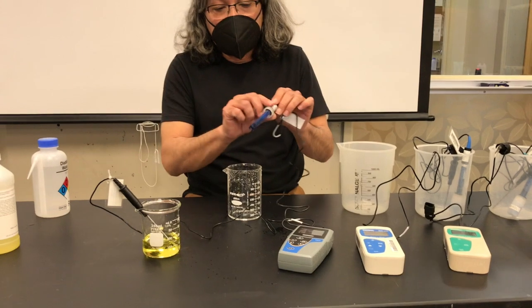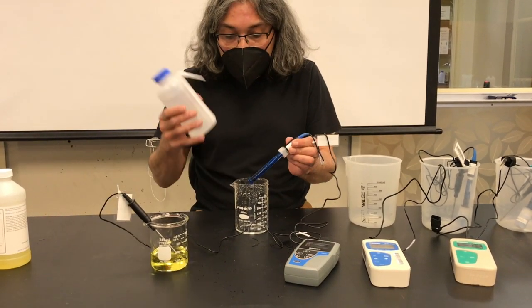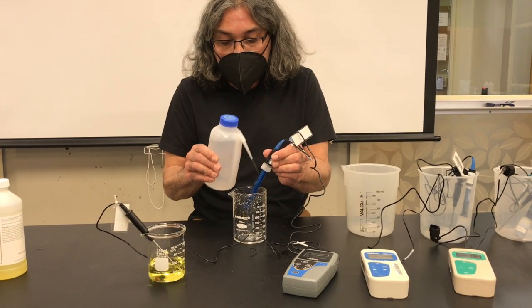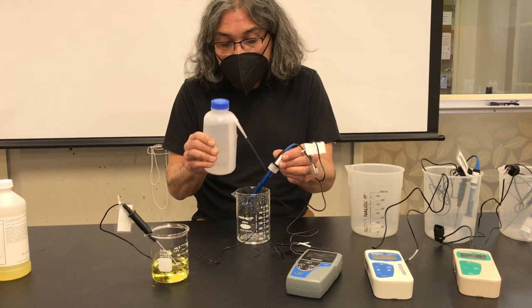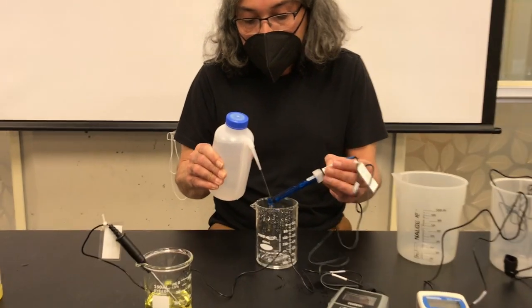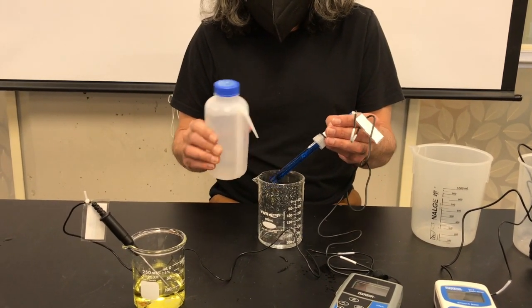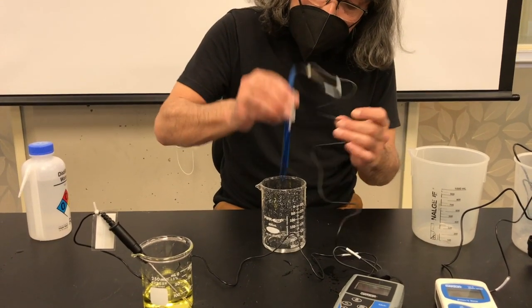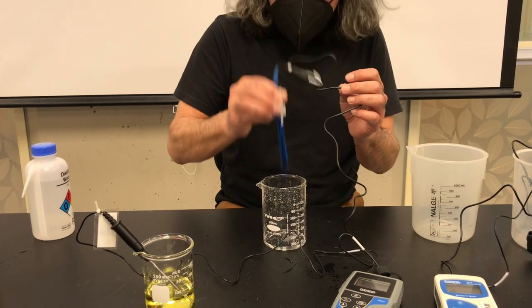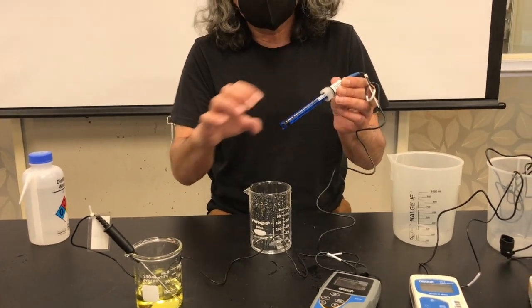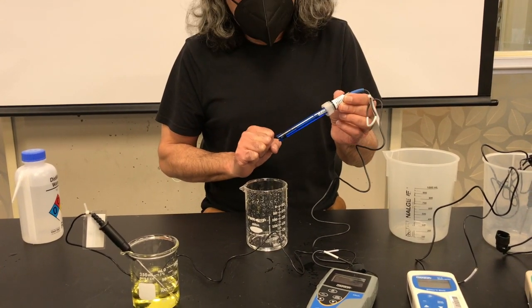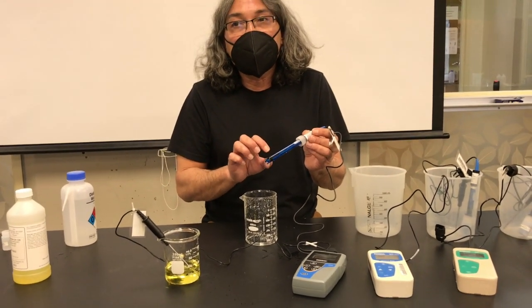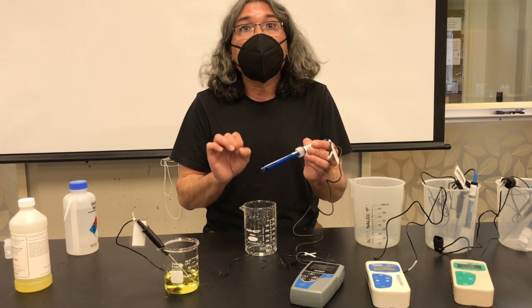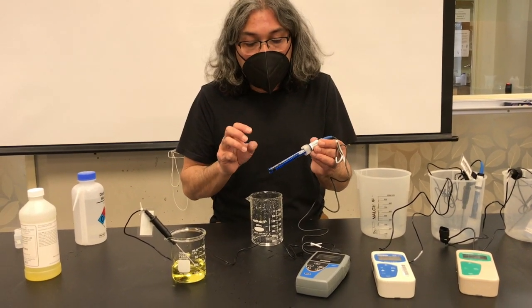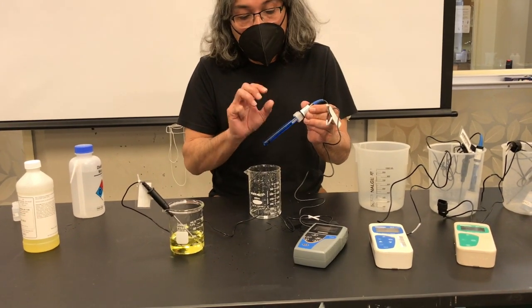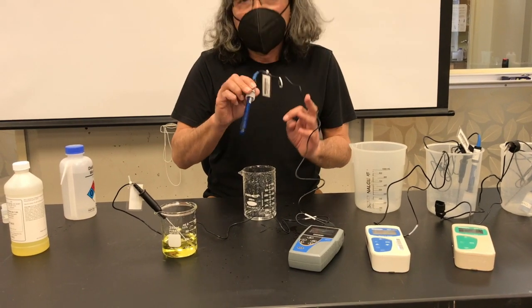Before you put it on your sample, you need to clean it. To clean it, you're going to use your DI square bottle and rinse the tip with DI water like this. Then after you're done rinsing, try to shake some of that water out. You should never wipe the probe with paper, because it's really easy to create an electrostatic charge that will give you inaccurate pH measurements. That's a very common mistake that I see people making, where they rinse and then dry it. You don't want to do that. Just rinse it, shake off as much water as possible, and then you're okay.